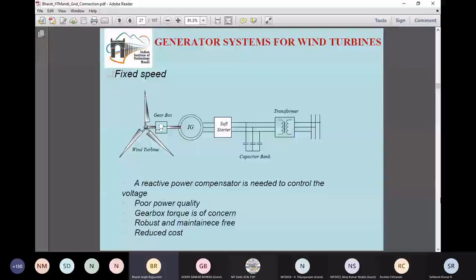And a drawback is also there. The drawback is that the reactive power requirement of this generator is an issue, since it is not able to produce the reactive power which is now required by the grid, because these wind turbines or wind energy conversion systems are now replacing the conventional synchronous machine which is able to produce reactive power. So this scheme was very popular, in India as well as abroad.